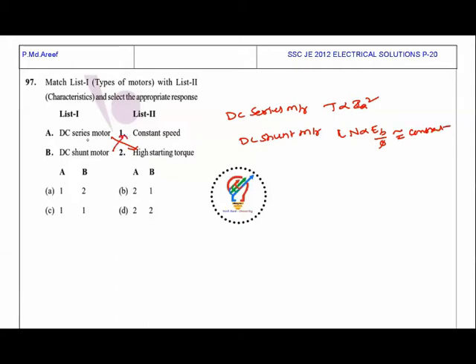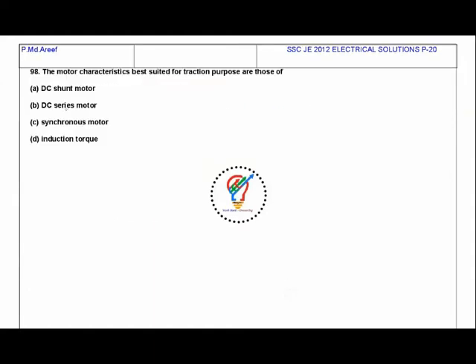Next question: the motor characteristics best suited for traction purpose. First preference is given to DC series motor. Second preference going to induction motors. Nowadays with advancement of power electronics, we are using induction motor drives in traction purposes.